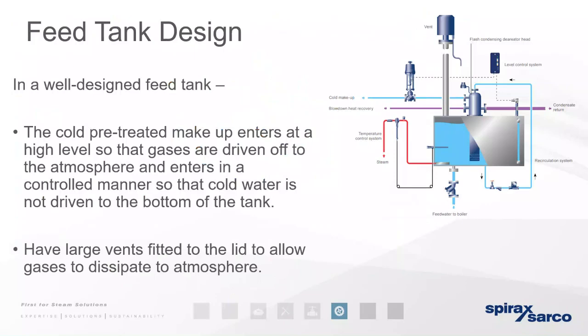So as we were talking about with the feed tank, this reiterates that the cold pre-treated makeup water enters at high level, so the gases are driven off. This means we're trying to remove the oxygen by creating the deaerator head, and we're preheating the water going in there. On the right-hand side of the tank, you have a recirc system. The reason this system is here is that hot water will rise, cold water will sink. The recirc allows it to go back into the header and get some of that energy, but also to evenly spread the heat in the water, so that when you pull down to your boiler, there isn't a cold spot at the bottom, and you're getting the ideal temperature throughout the tank.